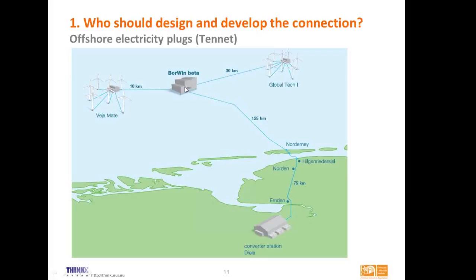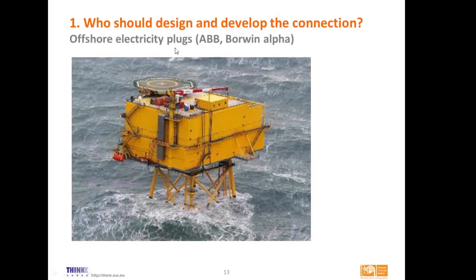How does this plug actually look? Here is a nice picture from the Elia homepage showing an idealized representation. But of course it doesn't really look like that — here is a picture of the only plug that has actually been constructed. It is roughly the size of a barn or a house. What you see at the top is not a trampoline — it is a helicopter platform so that people can arrive and do maintenance. This structure is actually more than a plug; it is a converter station. The very far offshore wind farms are connected to shore with DC, so this platform converts AC from the wind farms to DC for the cable to shore, and then onshore the DC is converted back to AC for the grid.